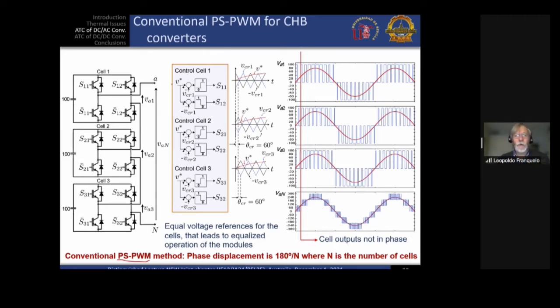With this modulation technique, we have the same reference that will give the same result for all of them, provided that this voltage is the same for all 3 cells. Assuming we have 100 volts, then we will have in each output A1, A2, A3 waveforms that are very similar but not exactly the same. When we sum them by making this connection, we have the voltage between the output and the neutral point, and instead of 3 levels, we will have 7 levels.